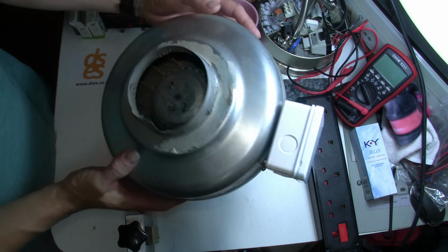Well, if I keep my Hioki probe on fan line but move the other probe from fan neutral to supply neutral, well, look at that. Fan line is live at 240 volts. But how can that be if the fan isn't spinning? Well, let's move the Hioki between fan neutral and supply neutral. And here's Johnny. What the actual heck?